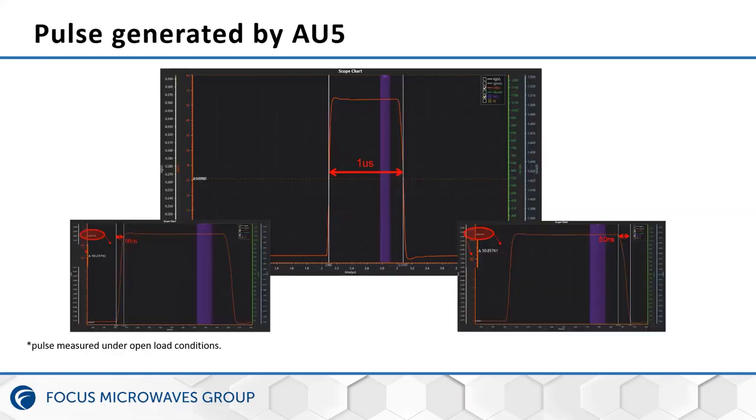This slide represents a typical pulse generated by the Auriga measurement system. Here we can see that the effective rise and fall time is around 50 nanoseconds for this pulsar head, and the pulse is pretty clean. There is minimal ripple and minimal overshoot. And this of course is required. Why? If we have a very clean pulse, we can make measurements much closer to the transient state, which gives us better isothermal measurements. It also gives us a wider sampling time so that we can have a good average signal within the pulse.